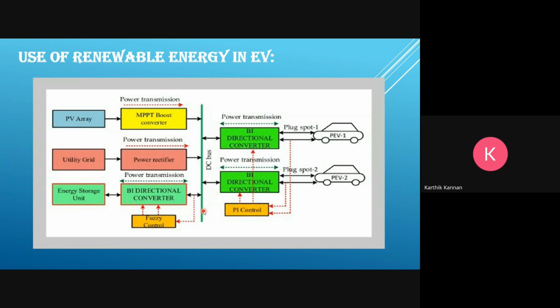PV array output voltage is 200 volts. Since we use an MPPT converter, you cannot just use any kind of PV array, battery storage, or bidirectional charger. If you decide to have a common bus, say 400 volt DC, then your PV array should be equivalent to that voltage, your battery energy storage system should be of that voltage, and your charger should be of that voltage, taking power from 400 volt DC. So you need a charger which works on 400 volt DC. You have to start from the charger, right?